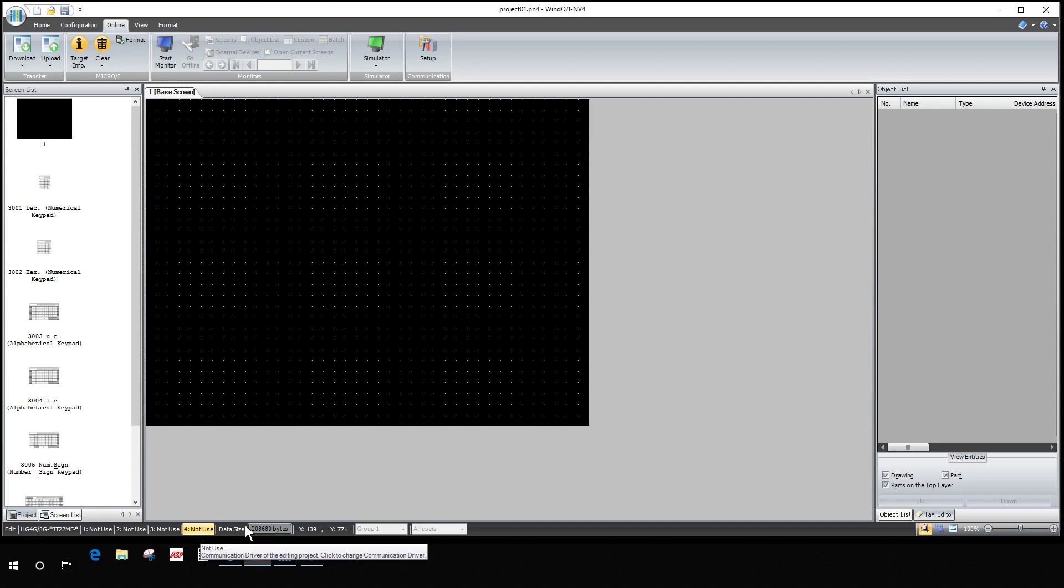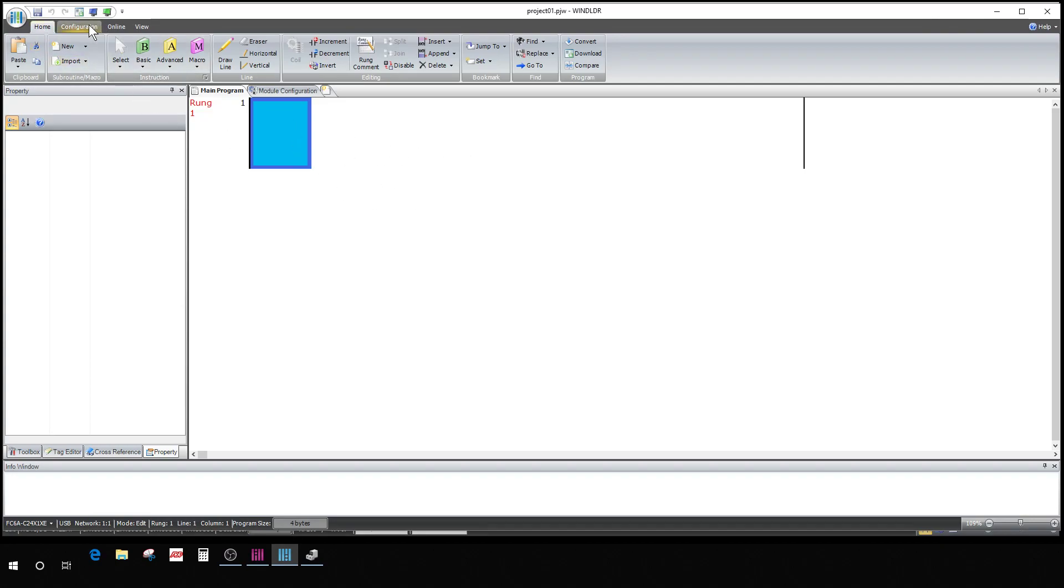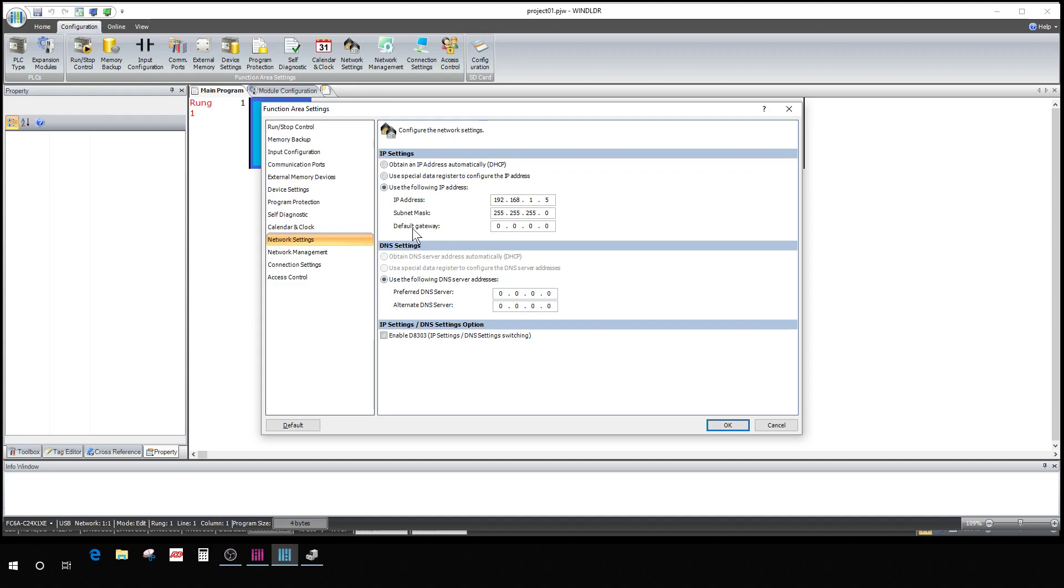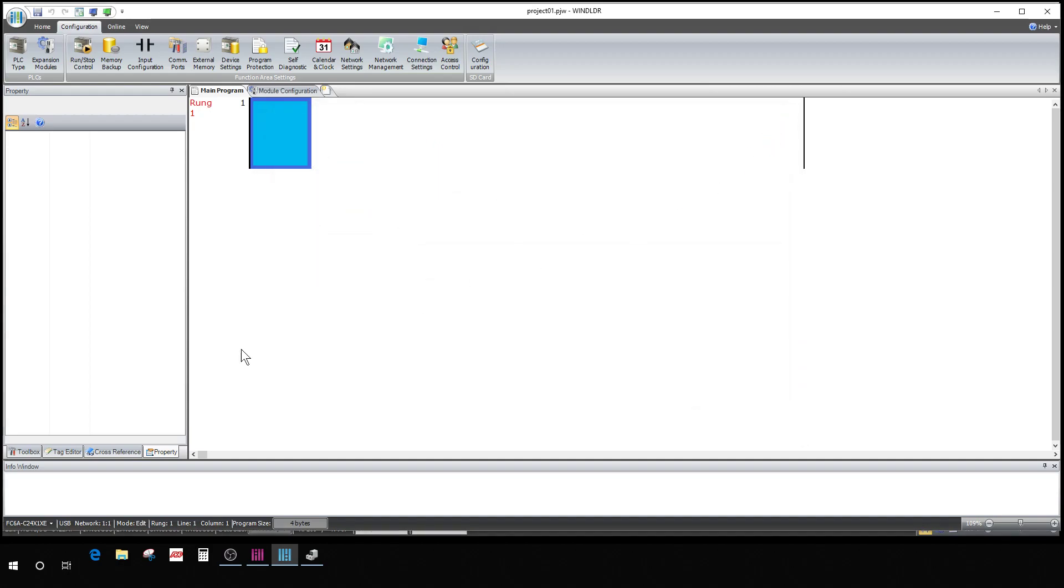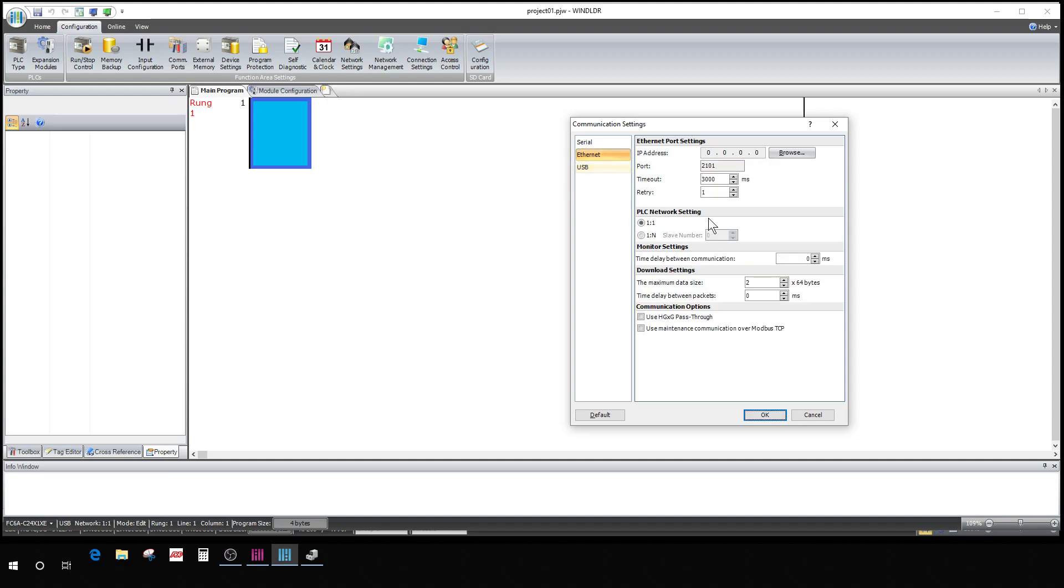Now as far as going in and setting up communication between the two of them: Let's start with the PLC. Once you have your firmware in, you can go in there and set up communication. Configure, network settings. This is the actual default IP address of your PLC: 192.168.1.5. This is where you can come in here and change this IP address if you want to. Now we come down here again, let's change this to ethernet.